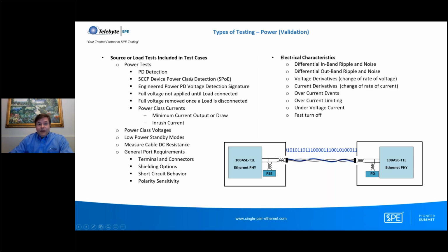Here are some of the tests we do run, however. So we have the power device detection. If you think about it, you have a field switch delivering power over its ports to the end device. It has to identify the device when it's connected on the end of the cable. So for general purpose single pair power over Ethernet operation, there is a protocol called the Serial Communication Classification Protocol. And that basically lets the PSE talk to the PD and determine what type of power it requires to operate.